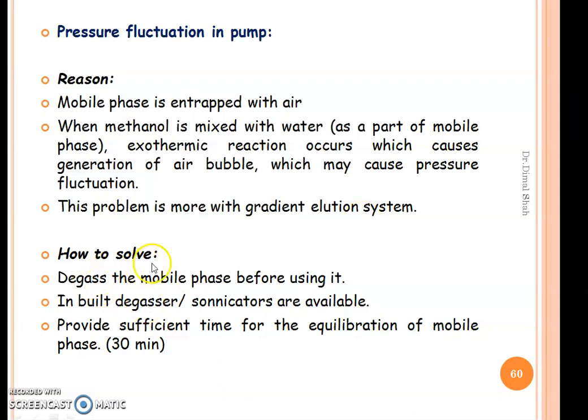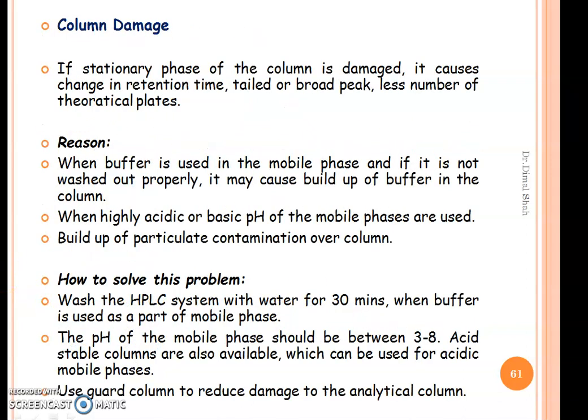Now how to solve these problems? Degas the mobile phase before you use it. Inbuilt degasser or sonicators can be used, as I already discussed, and provide sufficient time for the equilibration of the mobile phase, at least 30 minutes before you start your analysis.